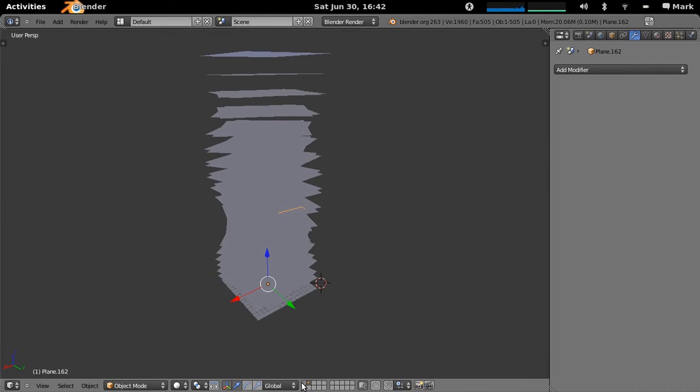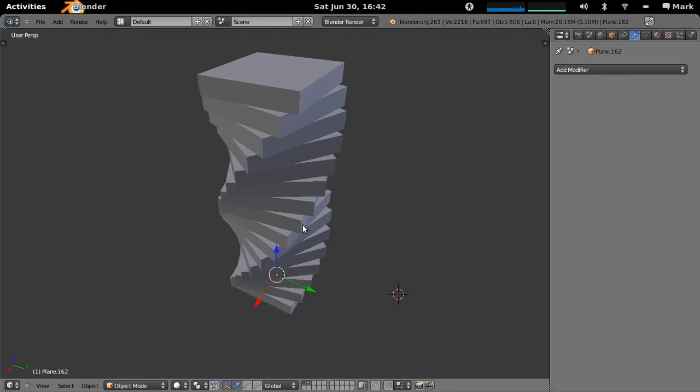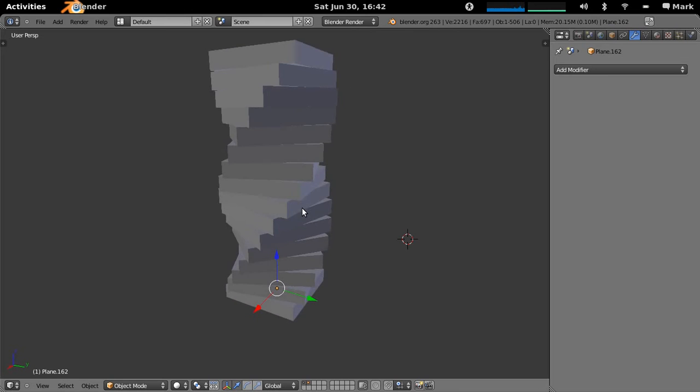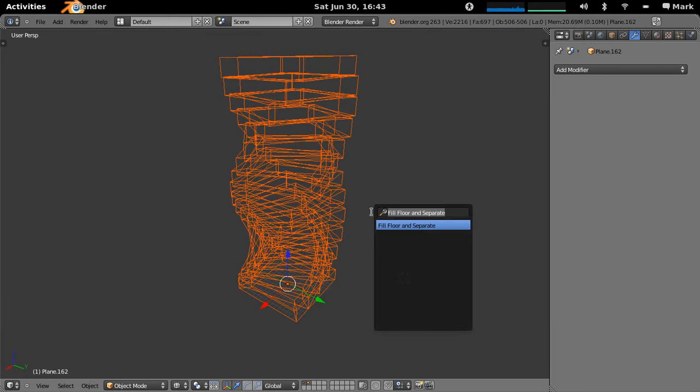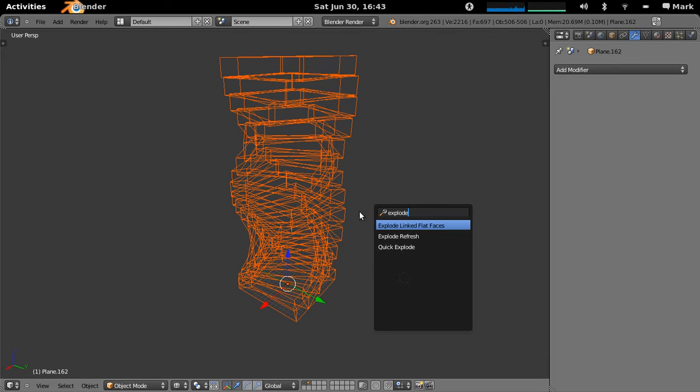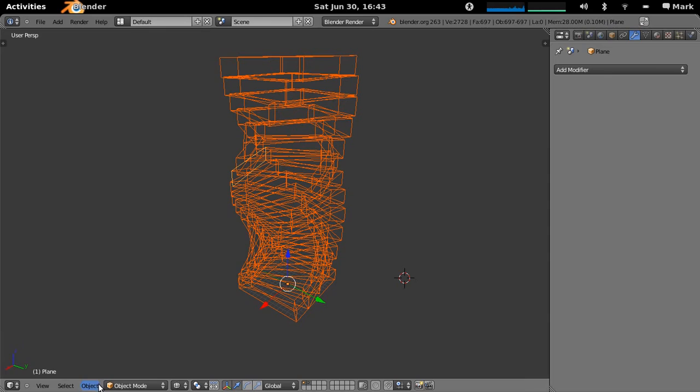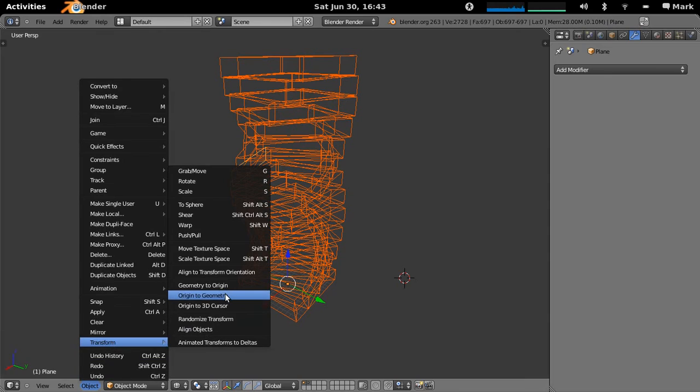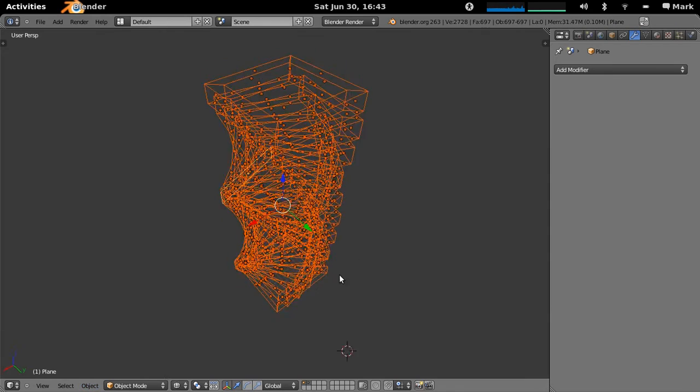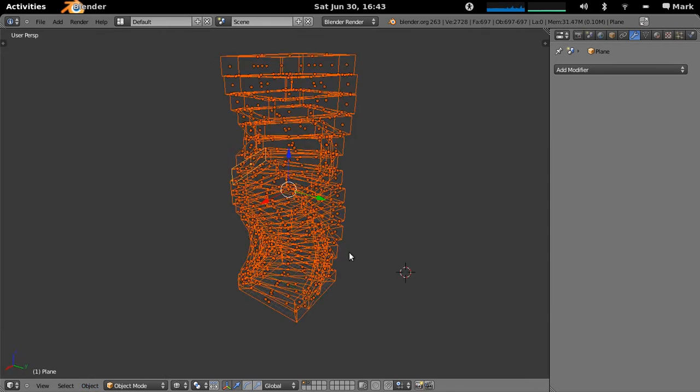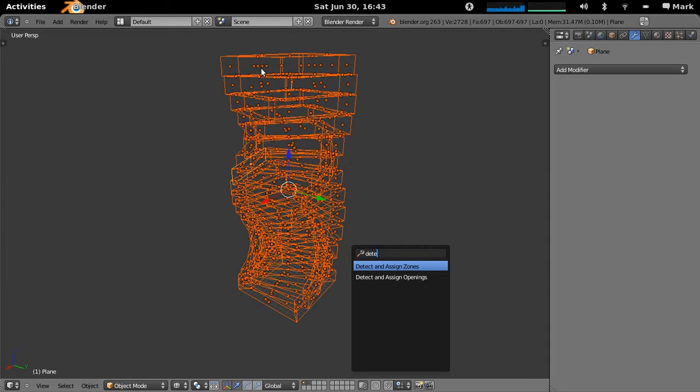And now if we join these two layers back together, you can see this is a complete building which we can actually now select all the objects. It will explode the linked flat faces which just goes through and actually separates all the faces out into separate objects and these will all become our separate heat transfer surfaces in Energy Plus. And then we're going to just detect and assign zones and this takes a little bit of time here. The actual interface freezes up just while it's calculating because it's quite a complex algorithm.